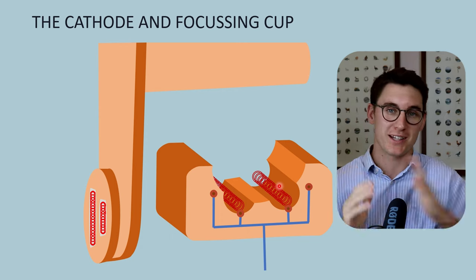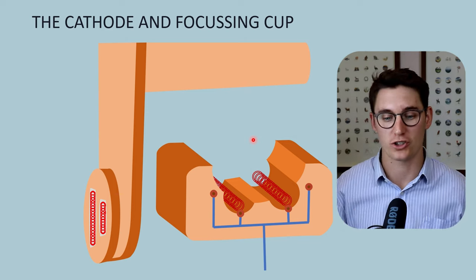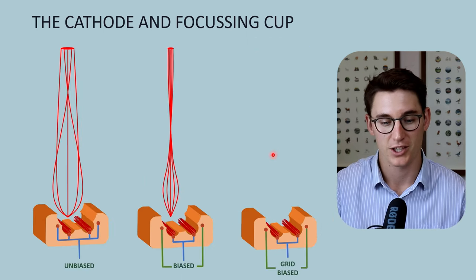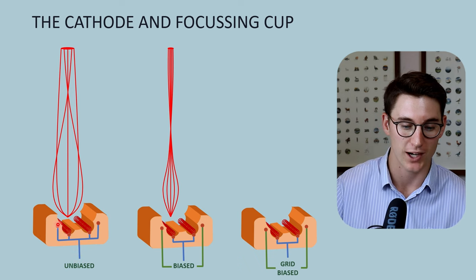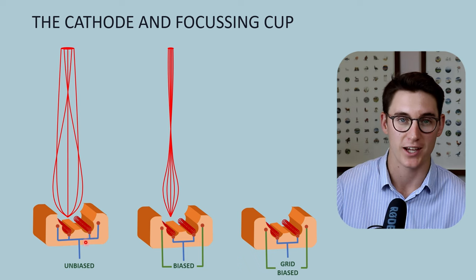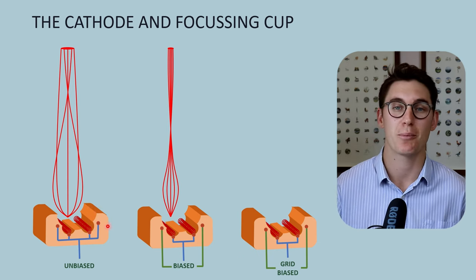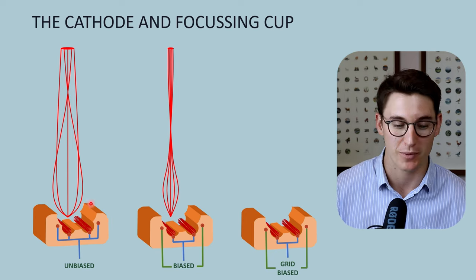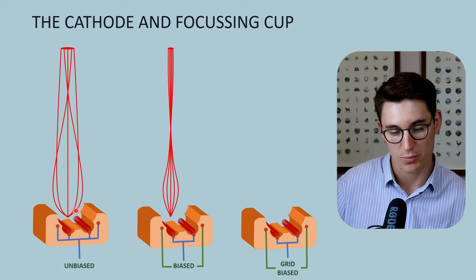It's the tube potential — that tube voltage — that accelerates those electrons. Without focusing, those electrons would spread out and hit the anode over a large surface area. This is where we use our focusing cup to focus those electrons down onto a smaller area on our anode. With an unbiased focusing cup, the electrical supply to our filament and to our focusing cup is shared. As we increase the current through our filament, we increase the current through our focusing cup, making it negatively charged. That negative electromagnetic field repels those negative electrons, focusing them down onto a smaller area.